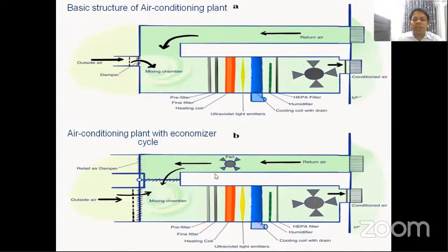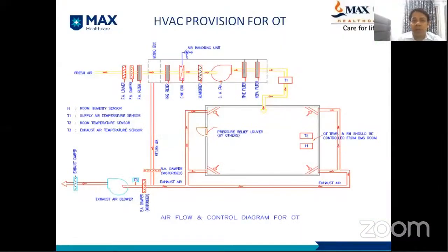Similarly, in the economizer, the extra thing is that one fan is added in the return pathway, and then the relief air damper is used. This is a very complex structure of the HVAC system. So if any part is not functioning properly, it can cause infection. This is the HVAC provision for the OT.